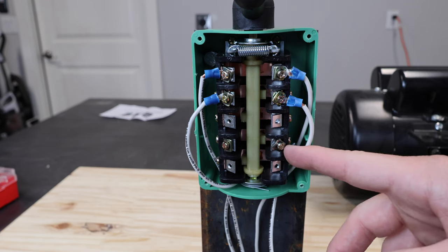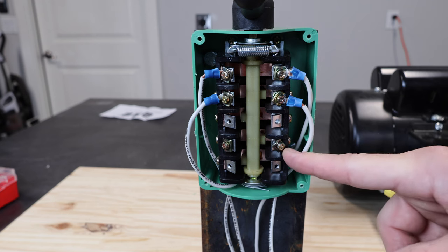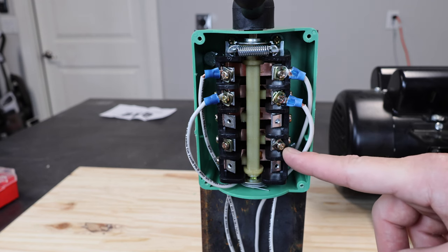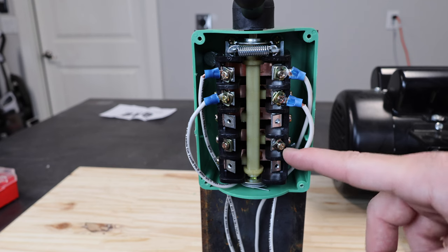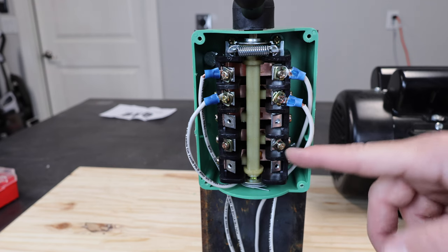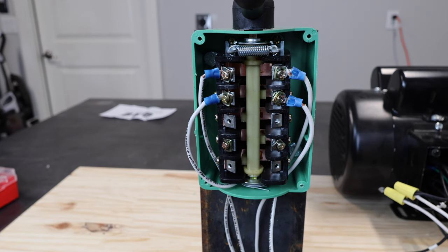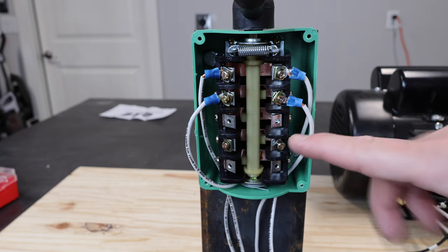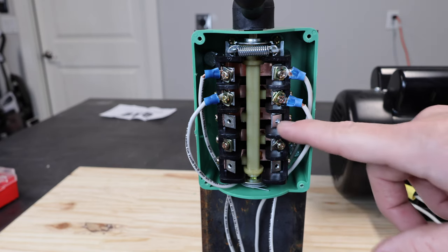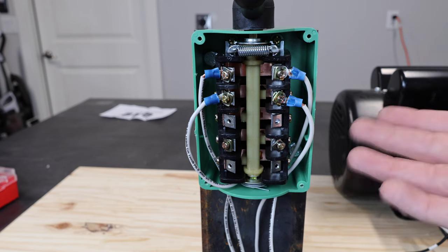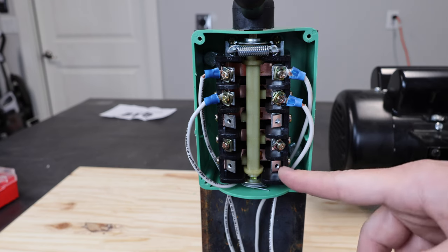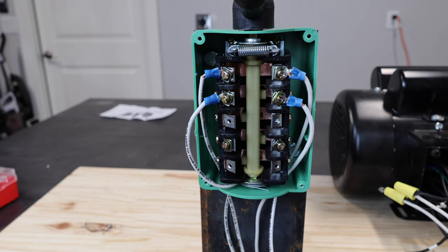Okay, so we're back over here on our right side. This one will be our L1 and T1. So, when I hook this one up, I'm going to have two separate wires. Just so that way, I can have one wire go to the motor and one go over to my distribution block. If, for some reason, the switch does not come with extra screws, you could actually use this secondary screw right here, which would make things so much clearer, so much nicer. But, it didn't come with the screws, or at least the one I got didn't come with them.